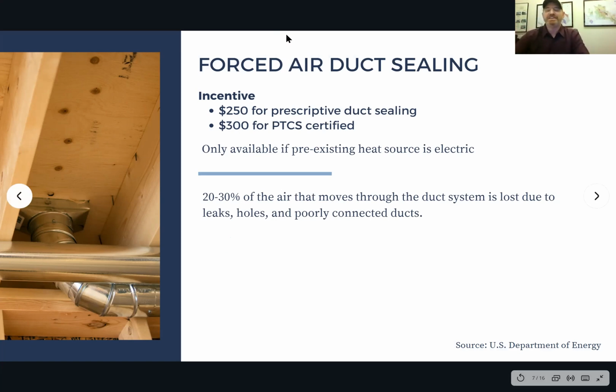Typically the ducting is either in the attic or in the crawl space. And one of the things that here in Ashland we do have is rodents. The rodents love to get into the insulation and they tear a hole in that ducting and it's leaking forever. And unfortunately, when the unit's on, depending upon where the air leak is, it will actually pull in the air from that source, whether it's under the floor or in the attic. So making sure the ducting is sealed, or if we're going to move forward here, hopefully to move to a ductless heat pump where you no longer have ducting whatsoever.